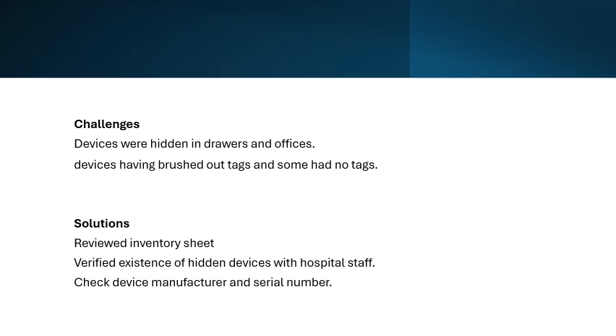Solution: we reviewed inventory sheets to help us find the missing devices, and we verified the existence of hidden devices with hospital staff. Sometimes we'd find a missing device listed in the inventory sheet, but it wasn't in the department, so we needed to ask the head charge nurse or the doctor about it to locate it. Lastly, if a device had a brushed-out tag or no HMG or PPM tag, we needed to check the manufacturer and serial number to match it in Asset Plus and confirm it was the right device, then print a new tag and put it on the device.